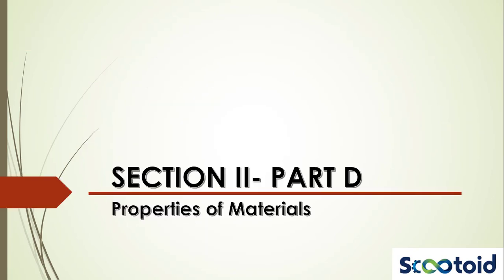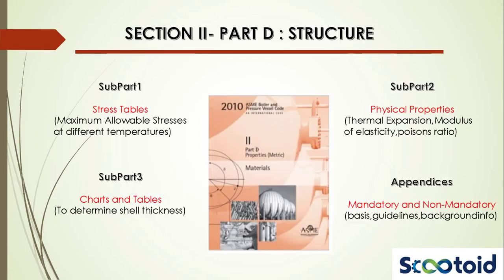Let's now move on to Section 2, Part D. Section 2 Part D of the ASME Boiler and Pressure Vessel Code covers the physical properties of the materials specified in Parts A and B. It is divided into these sections: Subpart 1 includes stress tables which give the maximum allowable stress for materials at different temperatures. The physical properties of these materials, such as thermal expansion, modulus of elasticity and Poisson's ratio, are found in Subpart 2. Subpart 3 provides charts and tables for determining shell thickness of components under external pressure. Mandatory and non-mandatory appendices provide the basis, guidelines, and background information for content in Subparts 1, 2 and 3.